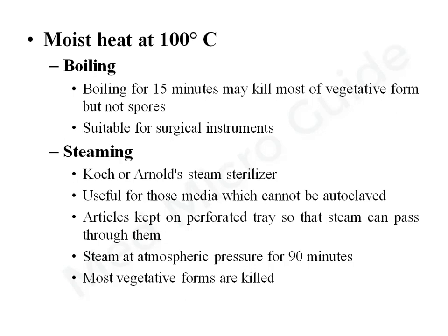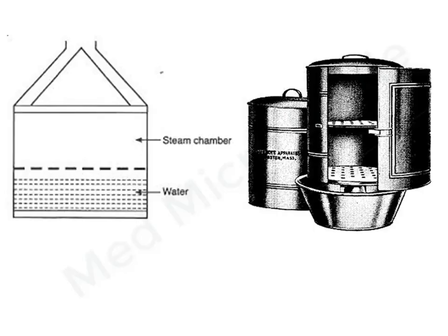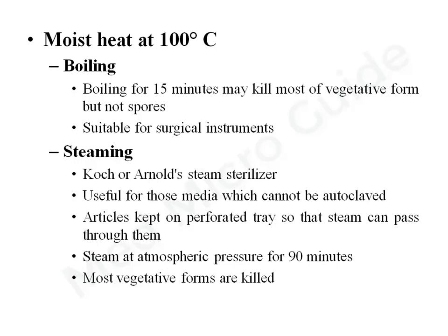Steaming is a process done in a Koch or Arnold steam sterilizer, which is a cylindrical instrument with a lid on top. It has a porous plate on which articles are kept for sterilization. At the bottom there is an electrical coil, and water is poured just above the coil. When the water starts boiling, steam circulates around the load and condenses to release latent heat onto the article. Steaming is done for 90 minutes at atmospheric pressure.